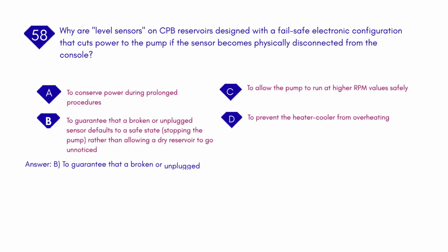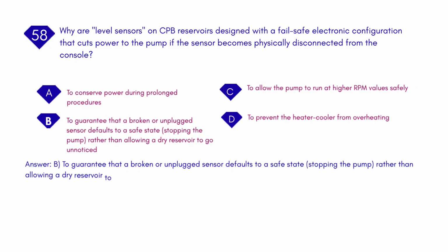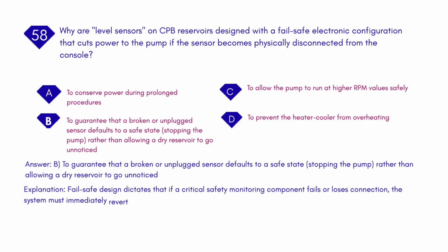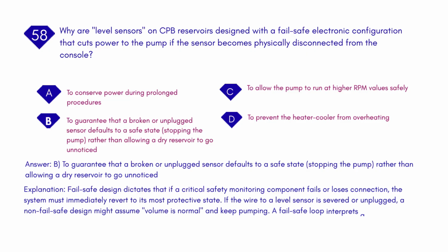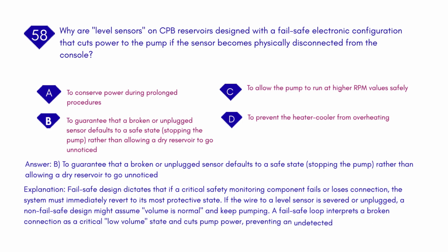Answer: B. To guarantee that a broken or unplugged sensor defaults to a safe state, stopping the pump, rather than allowing a dry reservoir to go unnoticed. Explanation: Fail-safe design dictates that if a critical safety monitoring component fails or loses connection, the system must immediately revert to its most protective state. If the wire to a level sensor is severed or unplugged, a non-fail-safe design might assume volume is normal and keep pumping.